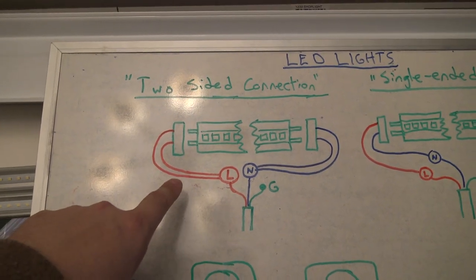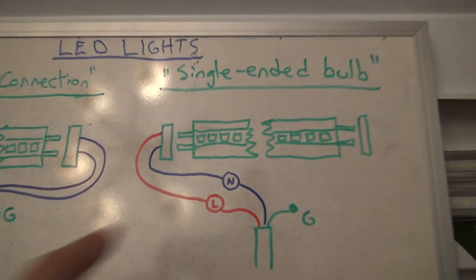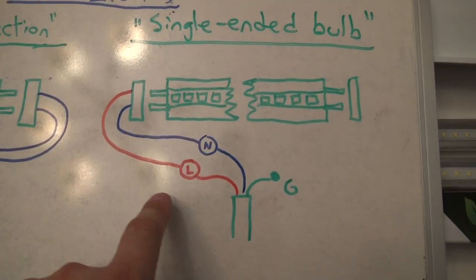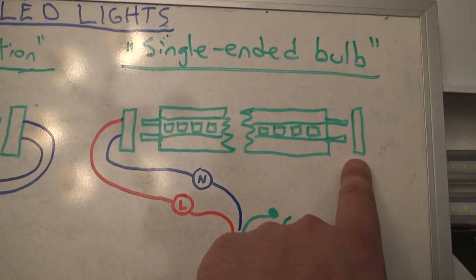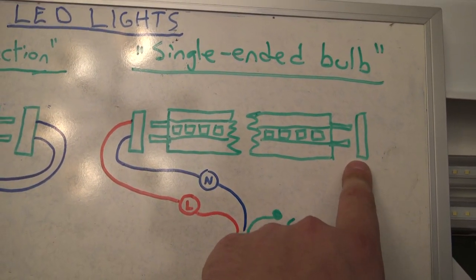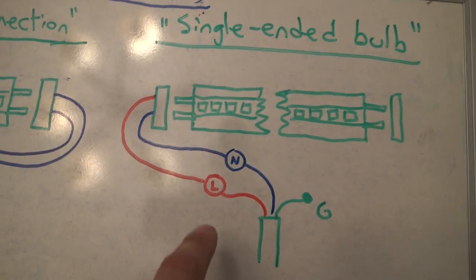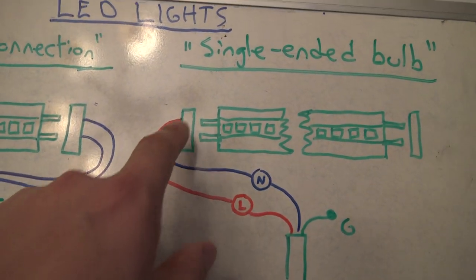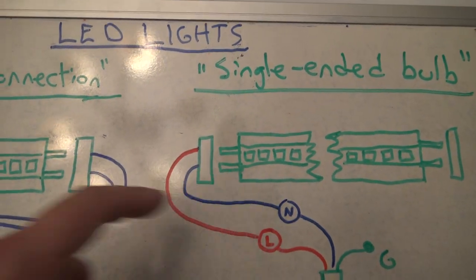So that's the first type you might run into, a two-sided connection. The other type that you might find is a single-ended bulb. And you'll notice the difference right away. There's actually a dead end to the bulb. This end doesn't get any power. It doesn't need any wires whatsoever. Because you're taking the load, and you're taking your neutral, and they're going to the two pins or the two sockets on one side of the bulb, and that's it.